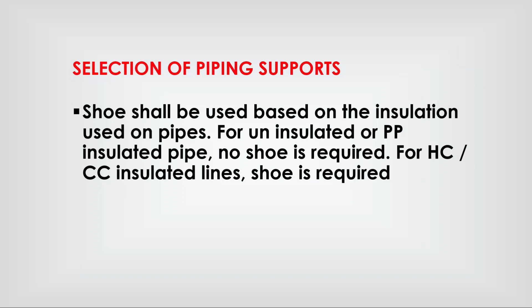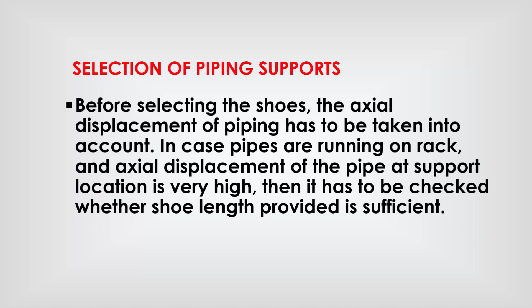Before selecting the shoes, the axial displacement of piping has to be taken into account. In case pipes are running on rack and axial displacement of the pipe at support location is very high, then it has to be checked whether the shoe length provided is sufficient. Slope lines should be rested using shoe supports only.